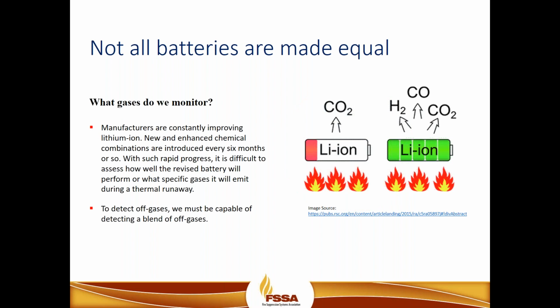So as we look at the batteries, we talked a little bit about what the components look like inside of the battery itself. We talked about the electrolyte liquids. Not all batteries are made equally. As you can appreciate, it's a very competitive environment. It's rapidly growing, with technology changes rapidly occurring. So there is no one set of gases, if you will, to look for or detect. You really need to take a holistic approach in off-gas monitoring. You can't just look for CO, you can't just look for hydrogen or methane.